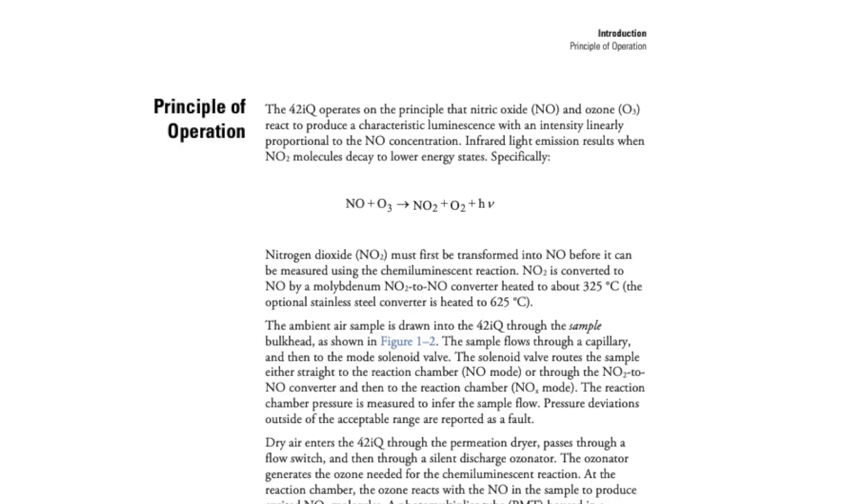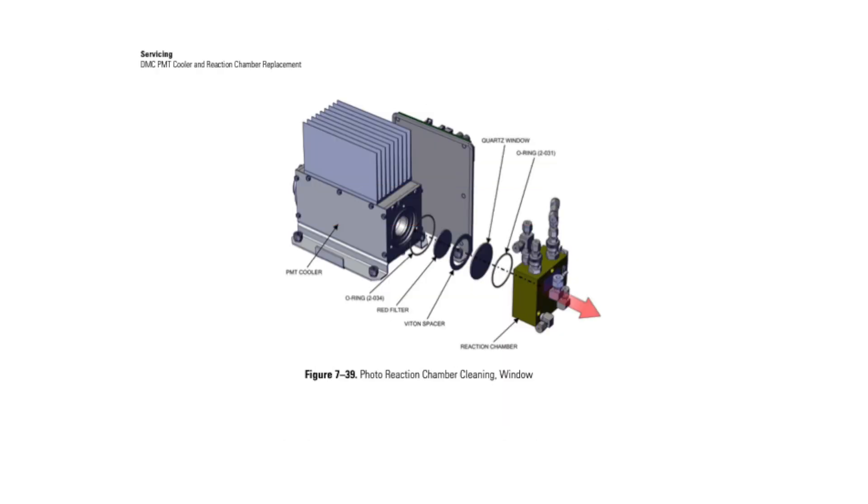The 42iQ operates on the principle of chemiluminescence. When nitric oxides react with ozone, they produce excited nitrogen dioxide molecules. The excited molecules emit photons in the reaction chamber, and those are recorded by the photomultiplier tube. The light recorded by the photomultiplier tube, or PMT, is then used to calculate the NOx emissions.